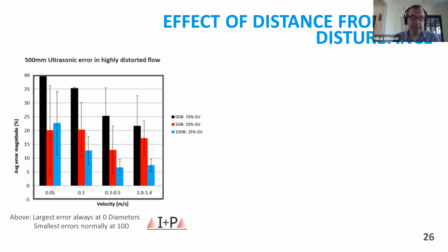A couple of things to point out here is that this was a really distorted flow. Basically, we got a gate valve, we opened it only 25%, and then we put it around a double bend, or maybe vice versa. But it was a really, really horrible flow profile. And what you'll see is that at any velocity, at 0 diameters the ultrasonics gave us the worst results. And then in most cases, all but one case, the best results were at 10 diameters. So if you look at this, getting further away is better. And again, you'll see higher velocities are better, generally up to 0.5. So again, getting further away is better.